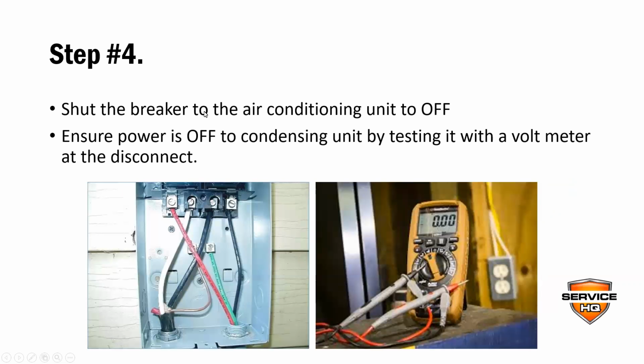Step 4, we're going to shut the breaker to the air conditioning unit off. And to ensure the power is off to the condensing unit, we test it with a voltmeter at the disconnect. This is a disconnect. This is usually on the outside of the house or where your air conditioner is located. And if you're not familiar with the voltmeter, I don't recommend you do any of this from here on out. You could probably just stop at that. Treat your drain pan, change your filters. I wouldn't call it good at that point, but it's better than a lot of people do, honestly.